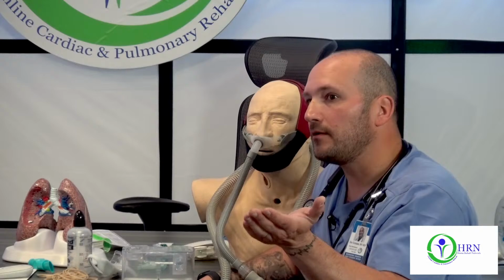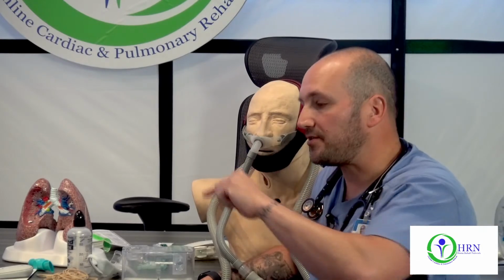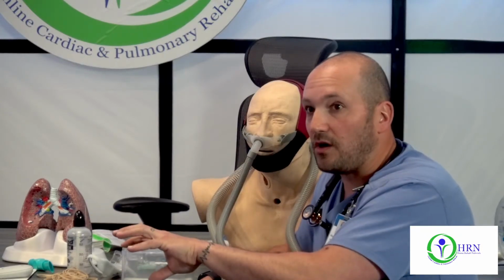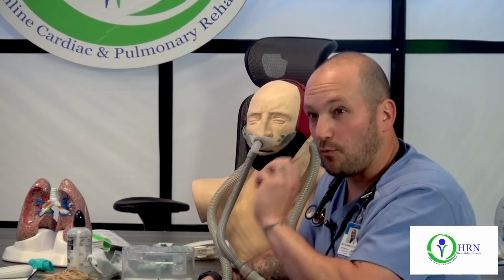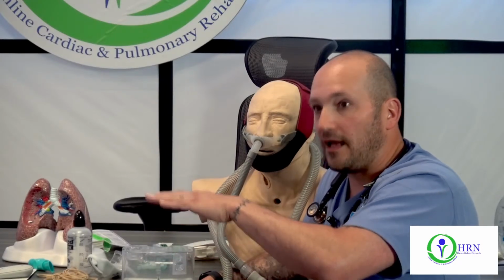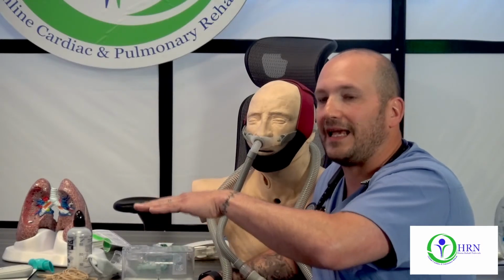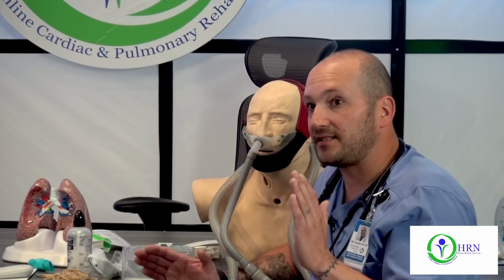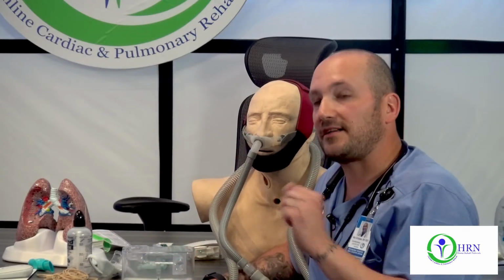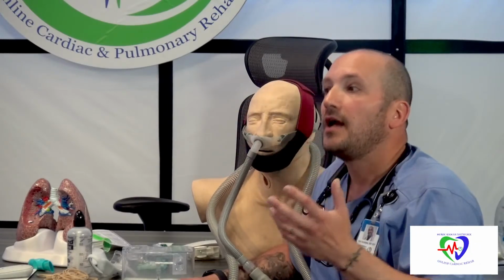And what would happen, you can't sleep without it? Yeah. So what would happen is you would press the ramp setting. It would give you a low pressure, like 1 centimeter of water pressure, with good airflow. And then every so often, it will slowly increase until 45 minutes has surpassed. Once 45 minutes has surpassed, it's giving you the full pressure. So it's giving you comfortability. It's slowly adding pressure, making you feel more at ease in a sense.